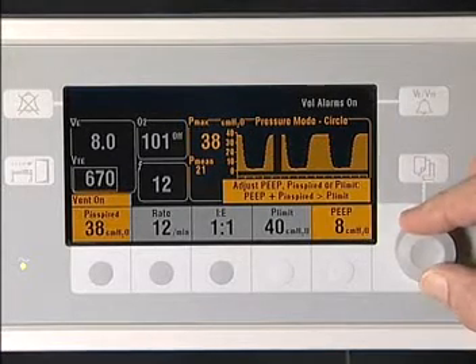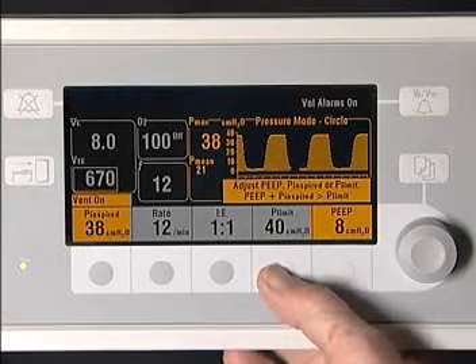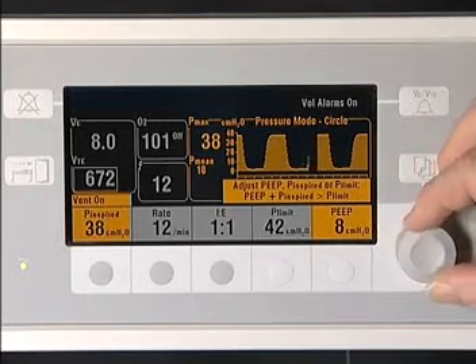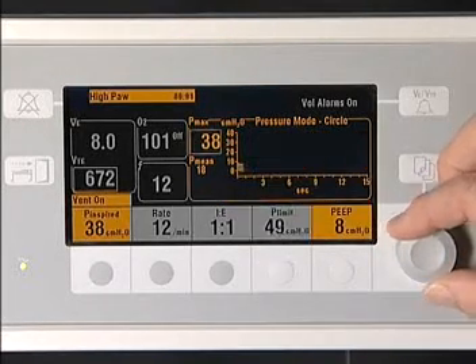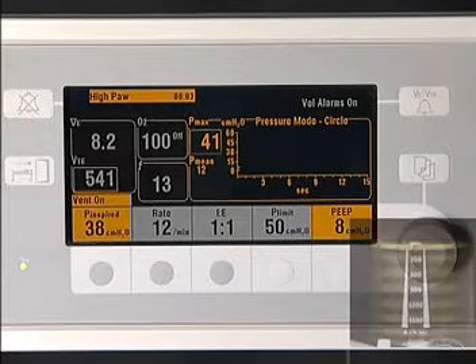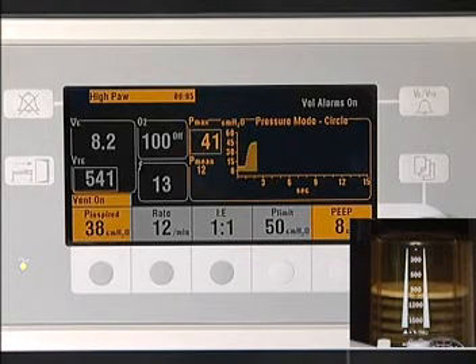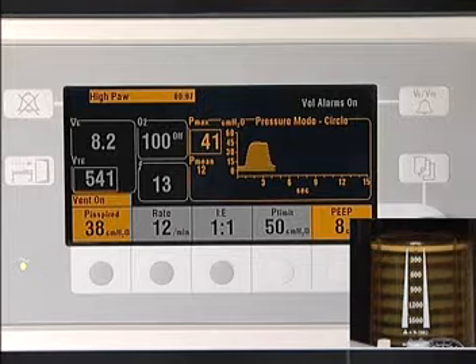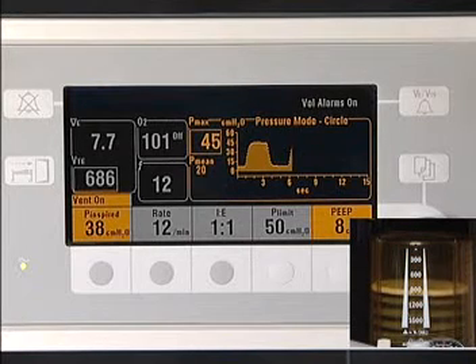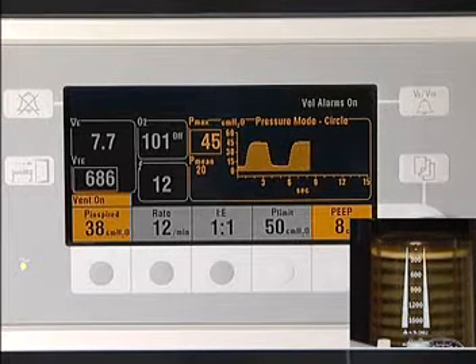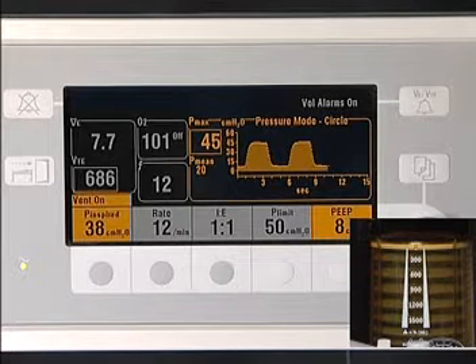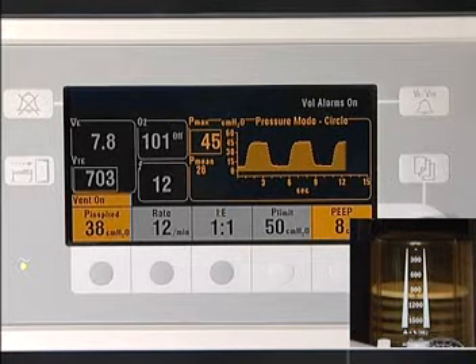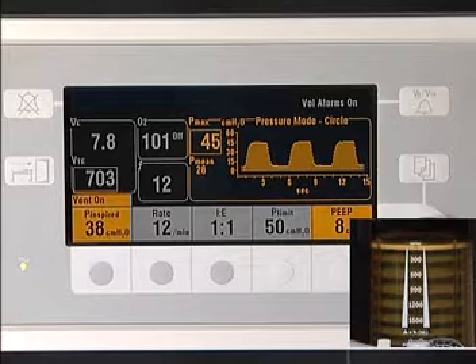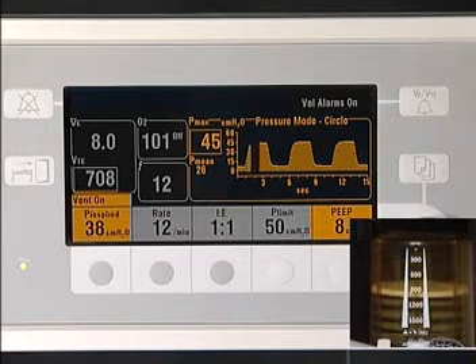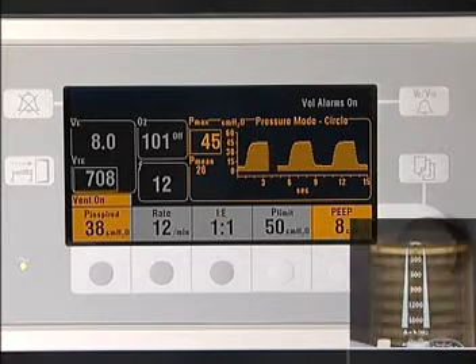PEEP is available while mechanically ventilating in either volume or pressure-controlled ventilation. It is accomplished by flowing gas across a diaphragm in an exhalation valve in the exhalation circuit. This gas then moves on to the bellows housing. Thus, if no exhaled gas is lifting the diaphragm, the restricting gas will cause the bellows to move down slightly, ensuring no degradation of the PEEP level throughout the E-time.